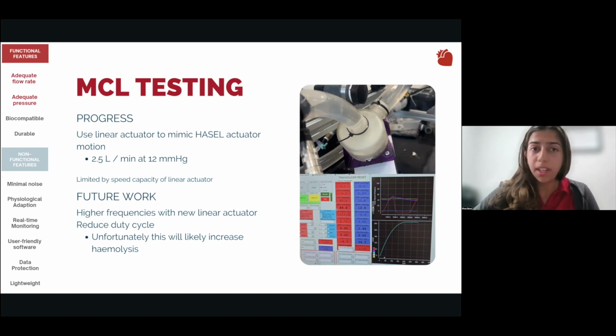From this, we estimate our HASELs will need to operate at 120 BPM or 2 hertz to achieve a flow rate of 5 liters per minute. Our main concern is that while HASELs only have a roll-off frequency of 120 hertz, a higher frequency will require faster prefill and will also result in an increased risk of damage to the blood cells.